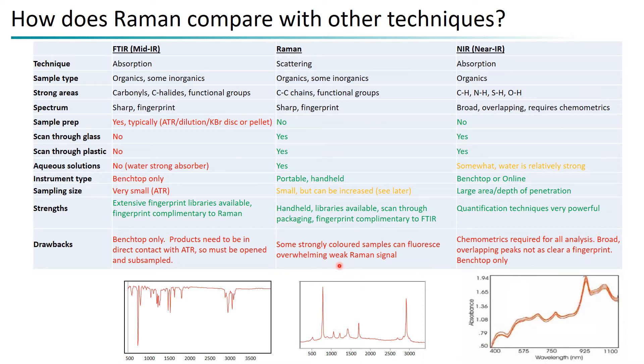With Raman, we get some influence from fluorescence — where the sample absorbs the laser light and emits wavelengths across a broad range, which can overwhelm the weak Raman signal. This is typically seen more on highly coloured materials and some natural products. We do have techniques for removing mild fluorescence, but for instance plant leaves could not be identified using this wavelength because they absorb the light and fluoresce back.